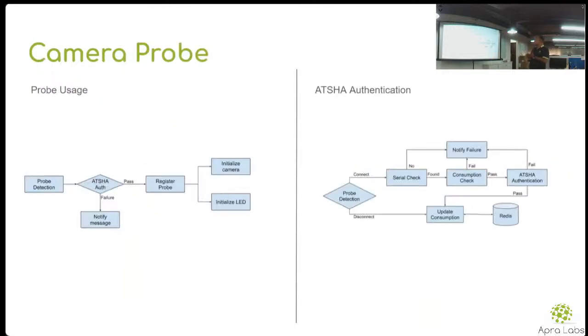I was talking about this ATSHA authentication a while ago. When a probe is connected, at that instance we check with the ATSHA chip what the serial number is. If we are able to get the serial number, we proceed, otherwise we say you guys are not valid. Next we do authentication. ATSHA authentication has some APIs where you get a challenge with a private key, and you give back the answer. If it is authentic, it gives you a response; if not, it says it failed.